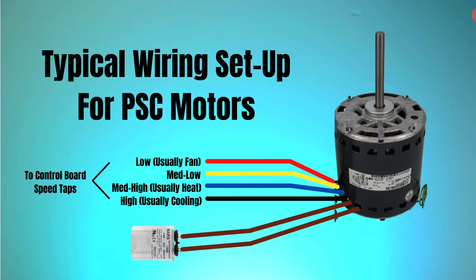Three or four high-voltage wires control the speed of the PSC motor — they're pretty simple to switch out, with high, medium-high, medium-low, and low taps attached to these blower motors. When a winding receives 120 volts from the furnace's control board, it starts up at that speed. But 120 volts isn't the only thing needed to start a PSC motor — it also needs a capacitor to provide the energy to get the motor up and running. The capacitor winding stays in the circuit the entire time the motor runs, which is where we get the P in PSC, for permanent.